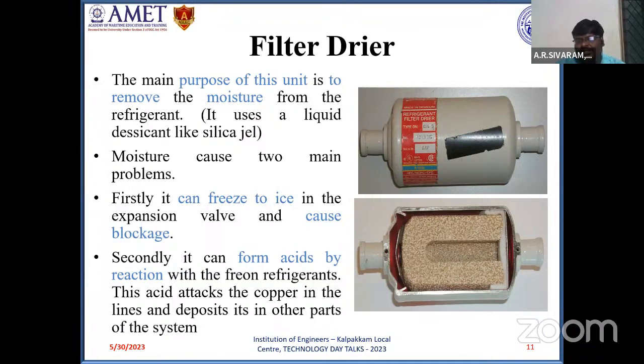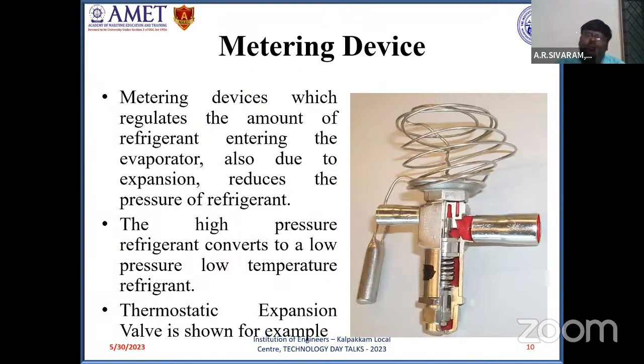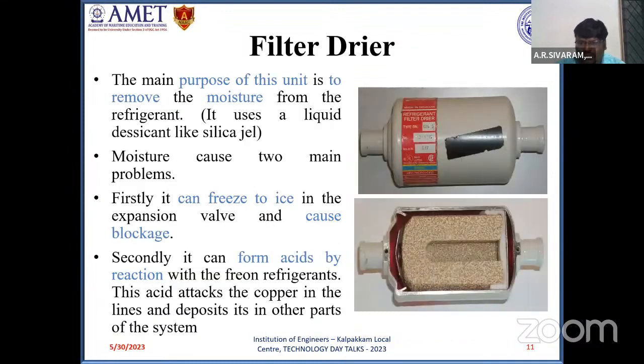The reason for having this filter dryer is that the temperature at the expansion valve outlet, for some systems, for domestic systems, can be 1 degree or 0 degree. At 0 degrees Celsius, any water vapor or moisture content will freeze into ice. And that ice formed inside the expansion valve will obstruct the flow of refrigerant. So before the refrigerant enters the expansion valve or metering device, this filter dryer removes the moisture content. If the filter dryer is not functioning, it will result in ice formation inside the expansion valve. It may cause a block in the expansion valve and obstruct the flow of refrigerant. Under such circumstances, in order to remove moisture content, the expansion valve has to be removed and the entire refrigerant has to be evacuated.